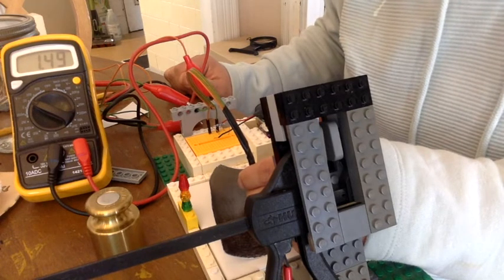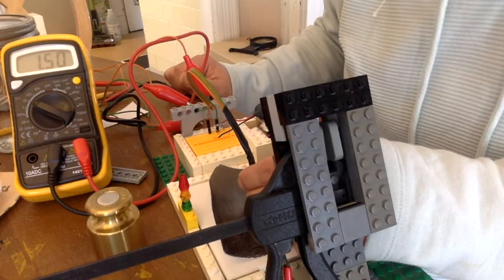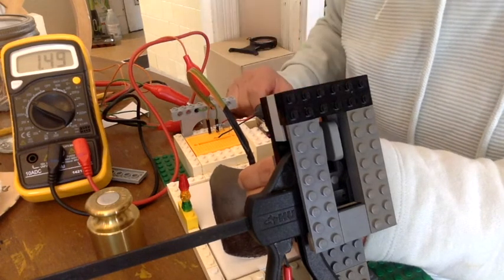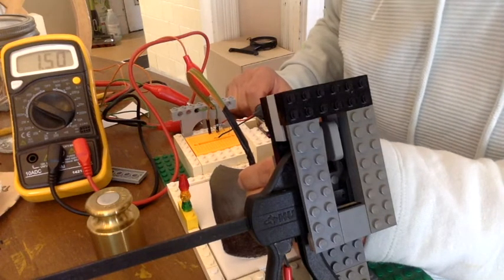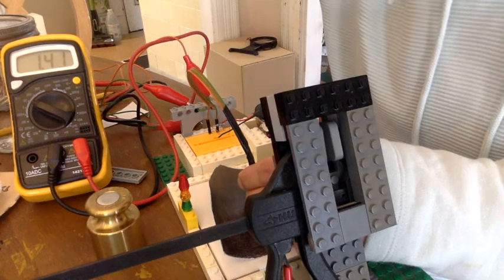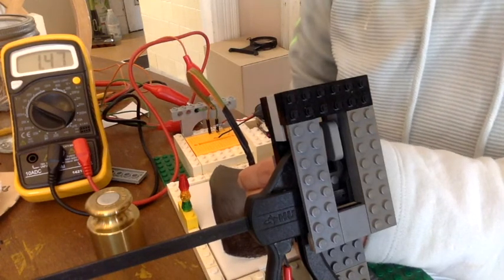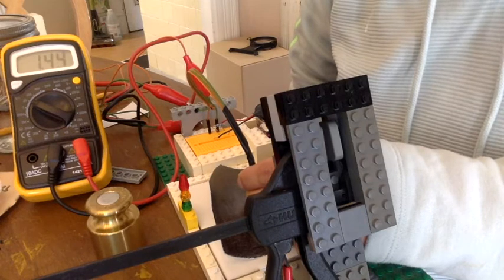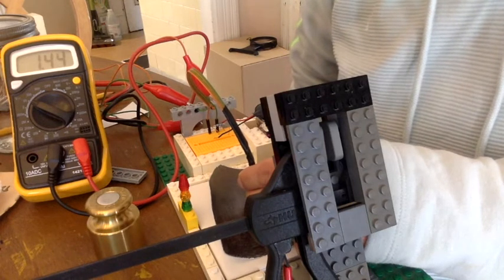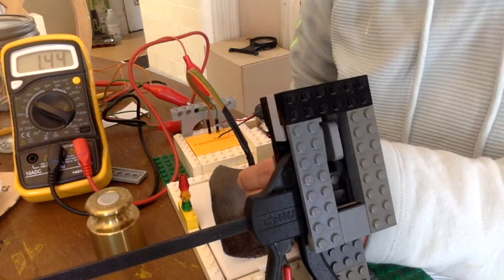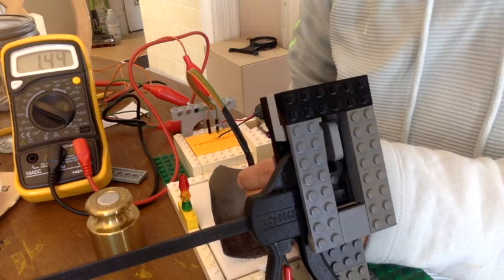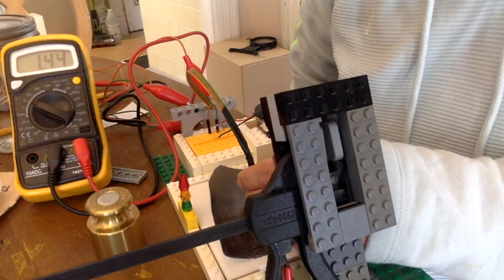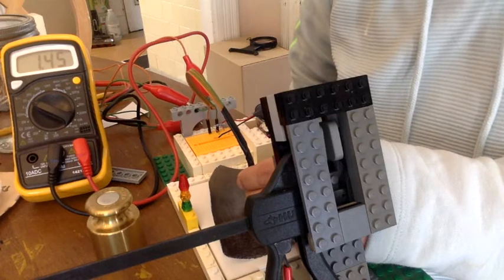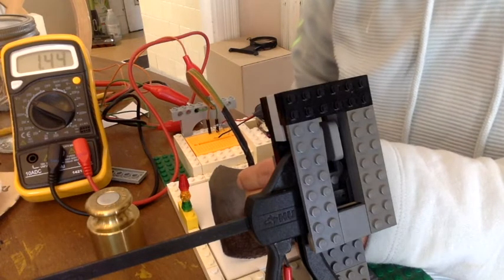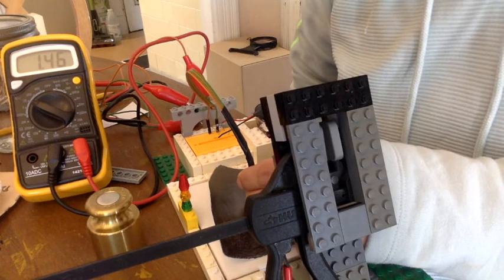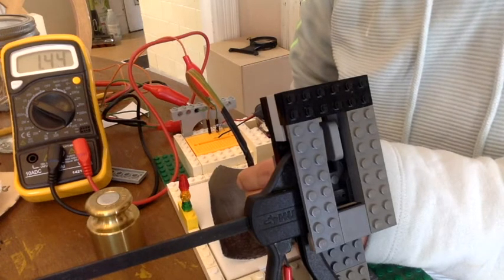The sample is not completely a square. I need to recut a square that's 11 by 11, which is the size of the tile there, and it's also a size which is 40 times the spacing between the probe tips, and that will allow us to avoid any correction factors based on the geometry of the sample. Because the sheet resistance, as we saw with the 2-point probe, if it's in a square configuration, then we're measuring the ohm square for the sample, and so there's no correction necessary for the geometry.